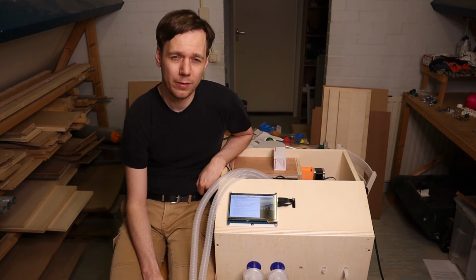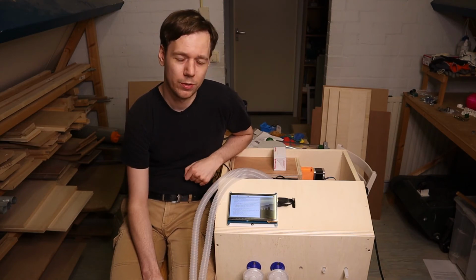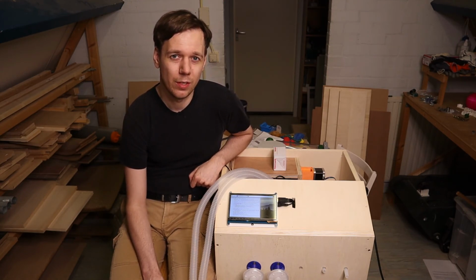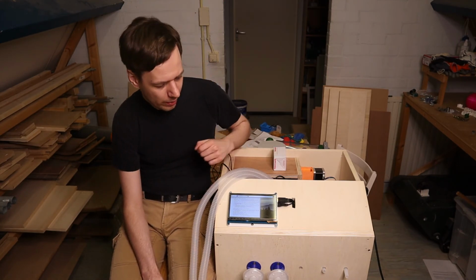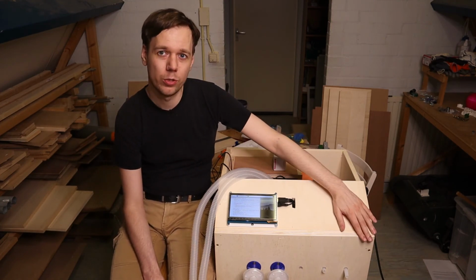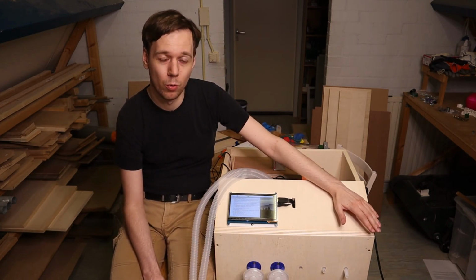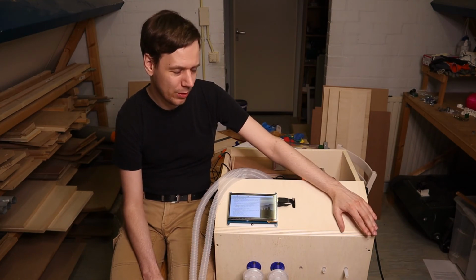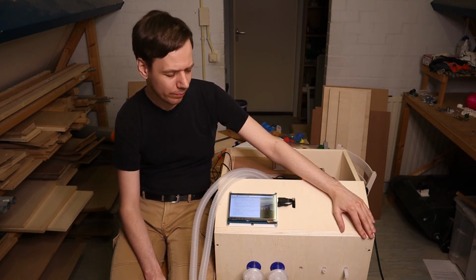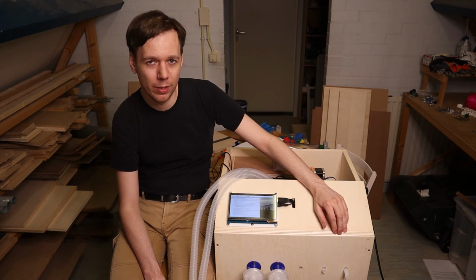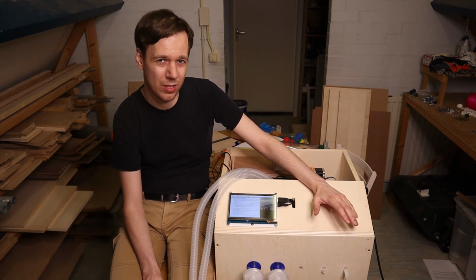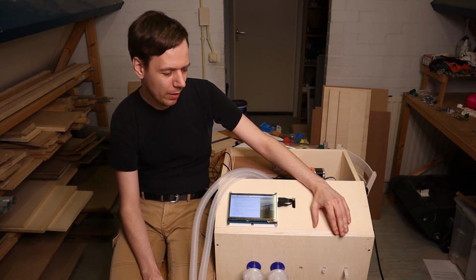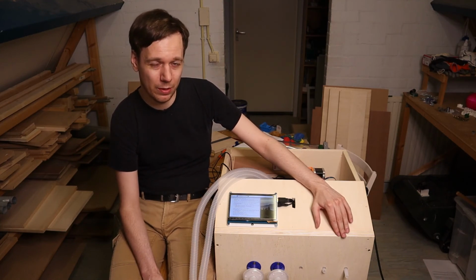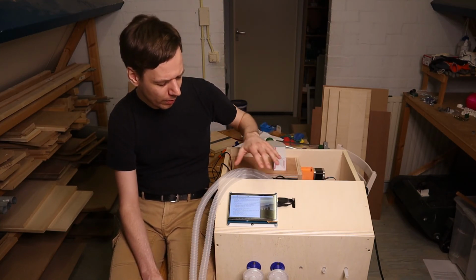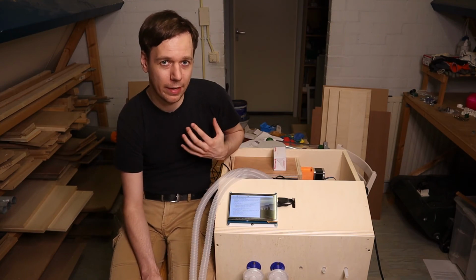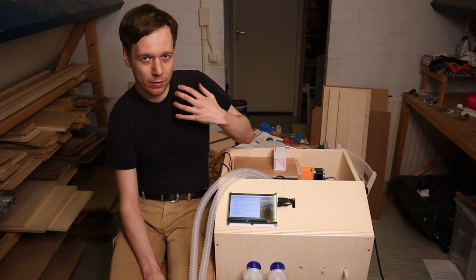There's a couple of other things that should still be added to this device. The first is a humidification unit. The issue is that the oxygen that you get from a bottle or anywhere else usually is bone dry. There's no moisture in there. And if you use a pressurized air source for the air, because that's arguably cleaner, then that would usually be completely dry as well.